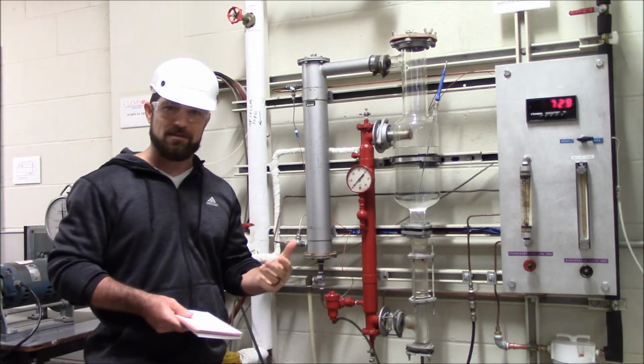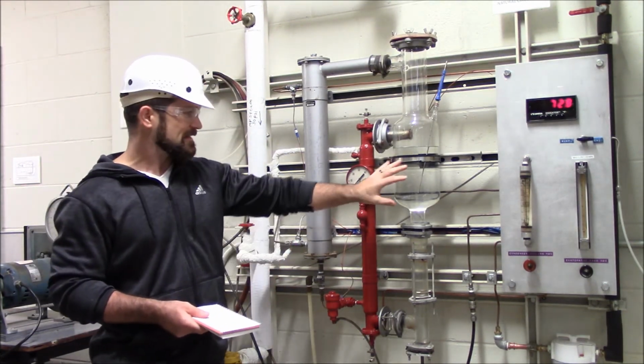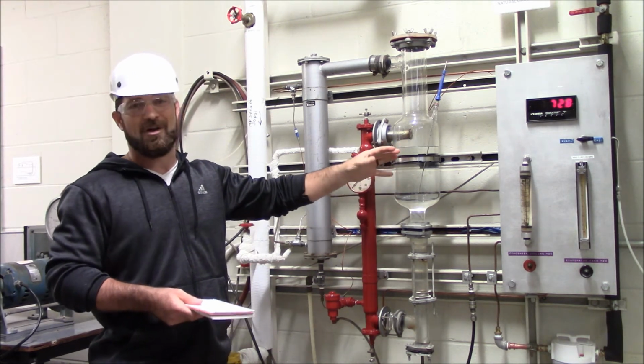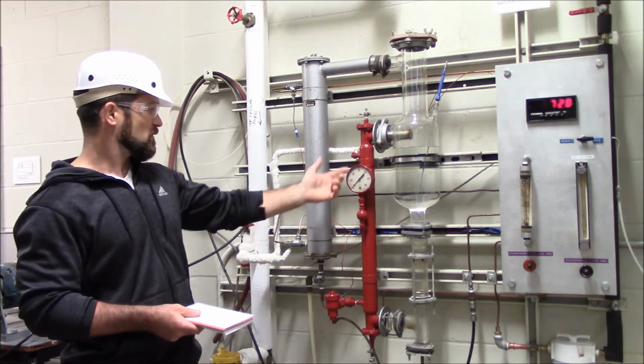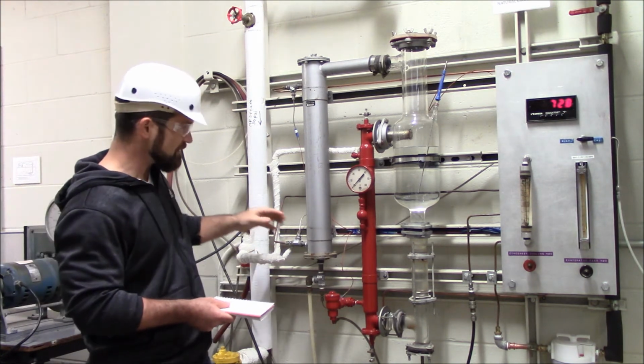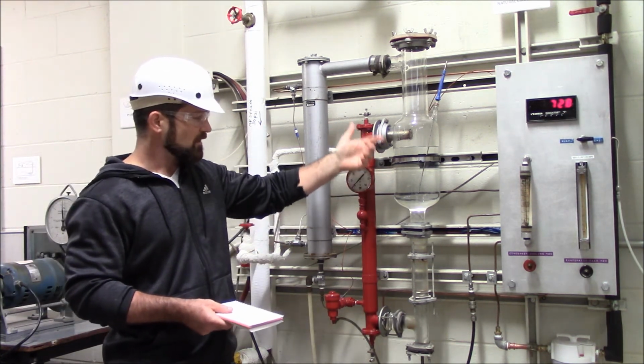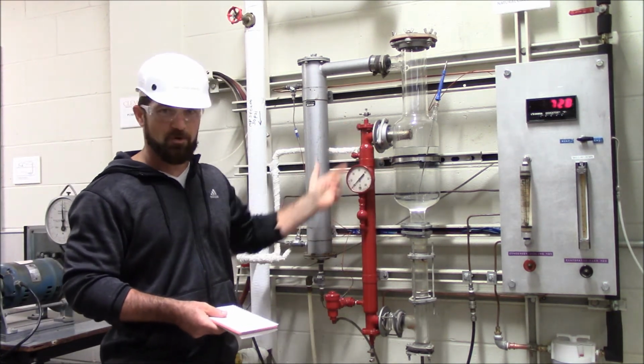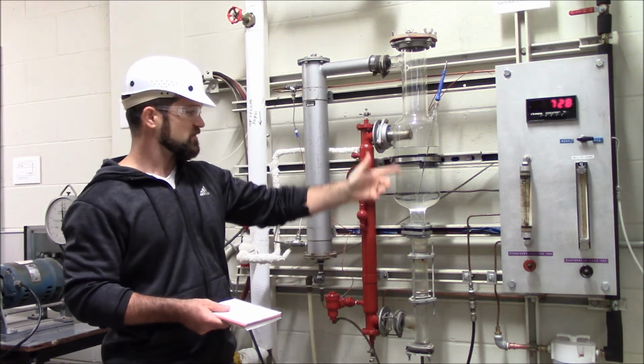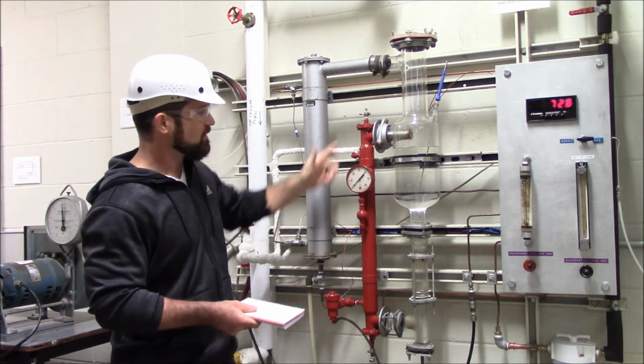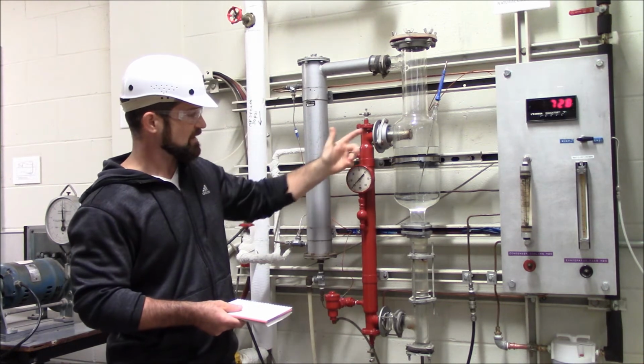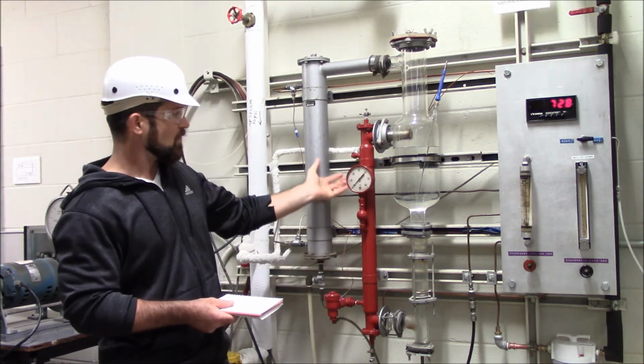Okay, so I recommend, if you want to get this heated up as quickly as possible, you probably want to use the highest steam pressure, which is going to be your max steam. So we turn this on. Once the water starts boiling, what you're going to see is the water start circulating in this system. So we're boiling the water in the system.